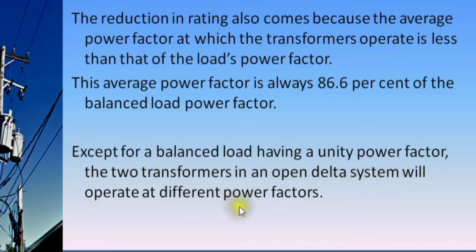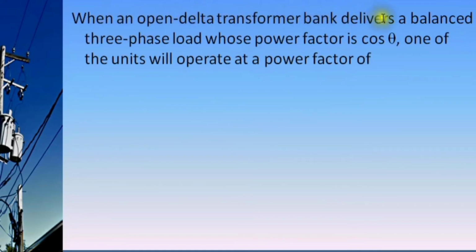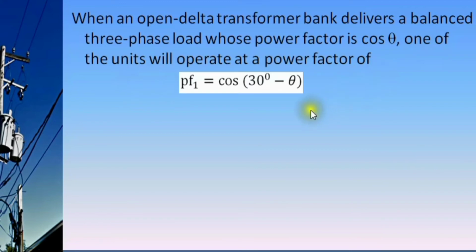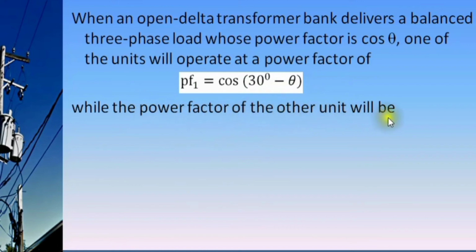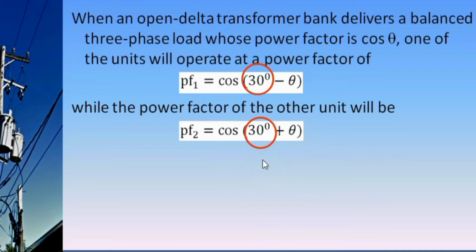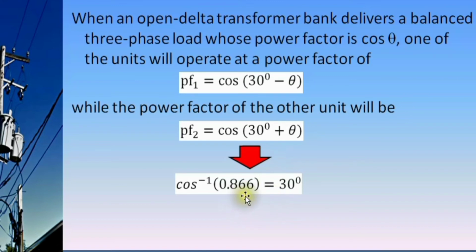Another thing, except for a balanced load having a unity power factor, the two transformers in an open delta system will operate at different power factors. Again, the open delta system will operate at 86.6% of the balanced load power factor, and each transformer will also operate at different power factors. When an open delta transformer bank delivers a balanced three-phase load whose power factor is cosine theta, one of the units will operate at a power factor of the cosine of the quantity 30 degrees minus theta, while the power factor of the other unit will be the cosine of the quantity 30 degrees plus theta. The 30 degrees in these equations comes from the inverse cosine of 0.866, or the inverse cosine of 86.6%. The angle theta here is the power factor angle of the load.